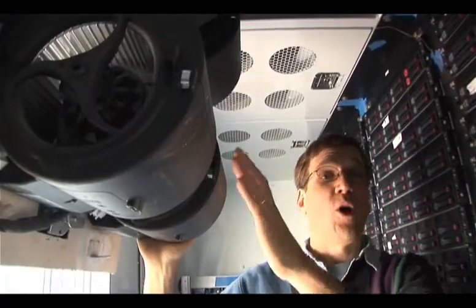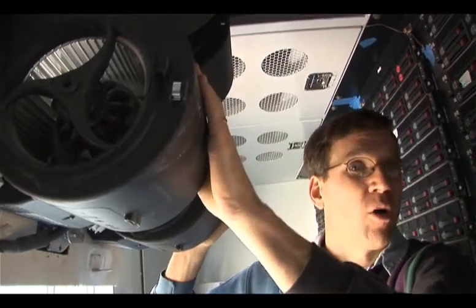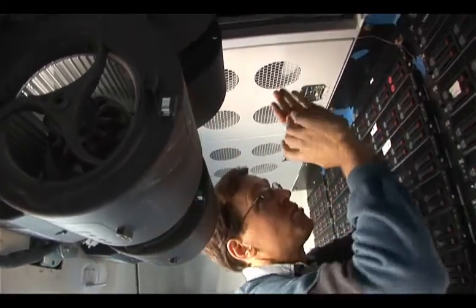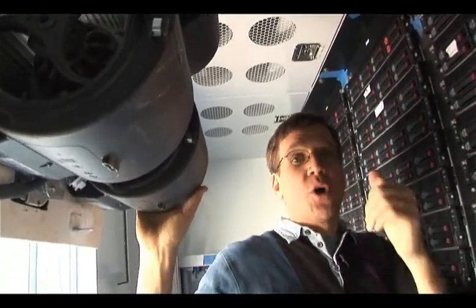We took the blowers right out of HP's modular cooling system liquid cool rack, a technology we already know about in production, and we took the heat exchanger out of that same rack. Those combined allow us to use warmer water and lower blower power.